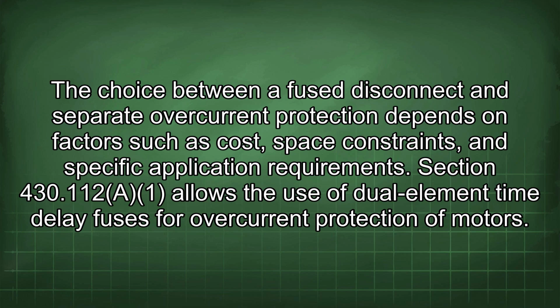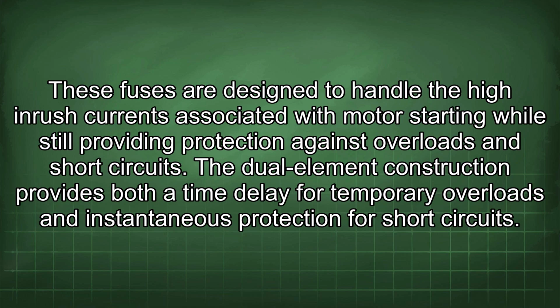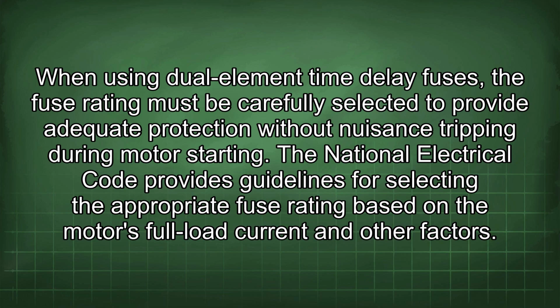Section 430.112(A)(1) allows the use of dual-element time delay fuses for overcurrent protection of motors. These fuses are designed to handle the high inrush currents associated with motor starting while still providing protection against overloads and short circuits. The dual-element construction provides both a time delay for temporary overloads and instantaneous protection for short circuits. When using dual-element time delay fuses, the fuse rating must be carefully selected to provide adequate protection without nuisance tripping during motor starting. The National Electrical Code provides guidelines for selecting the appropriate fuse rating based on the motor's full load current and other factors.